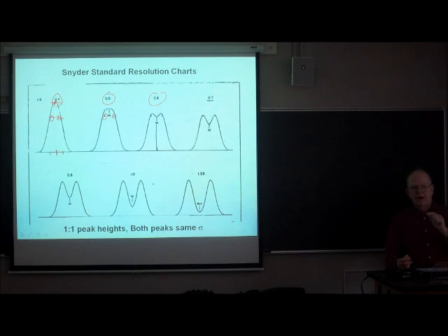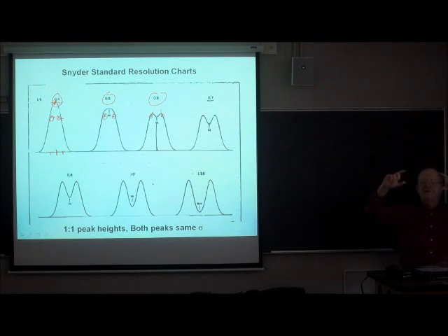Now, because the maxima are discernible does not mean that there's no analytical error. Because here's the dot, and there's the dot, and here's the peak maximum, and there's the peak maximum. And so both peaks are a little bit too high, and neither peak maximum is occurring at the right position on the volume or time axis. Both of these maxima are shifted inwardly from the true maximum.